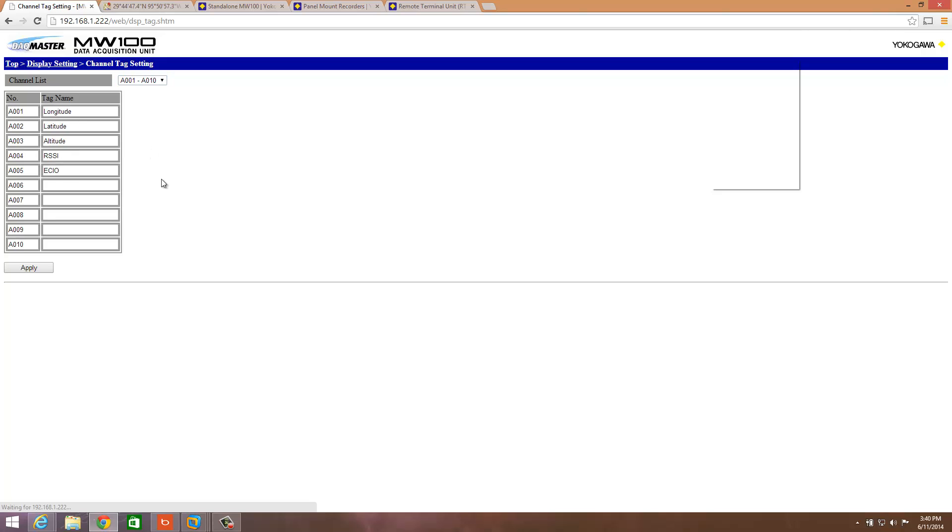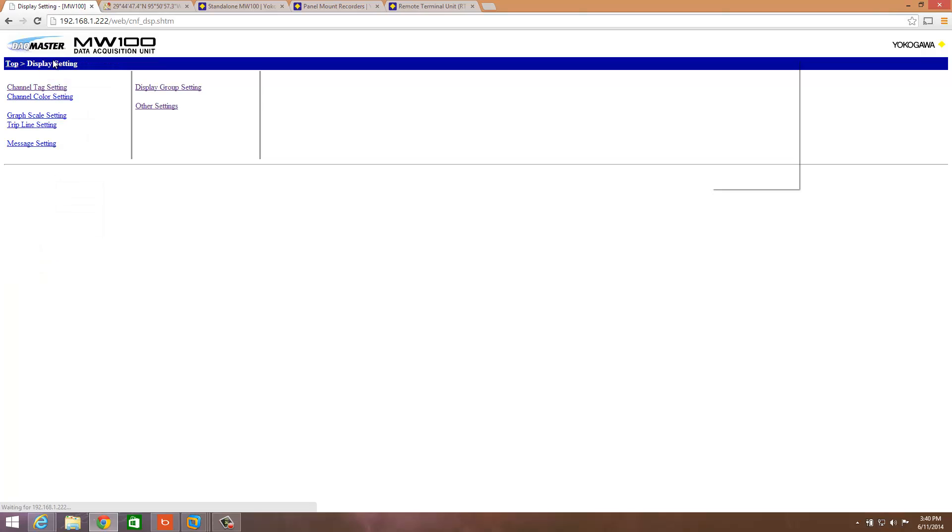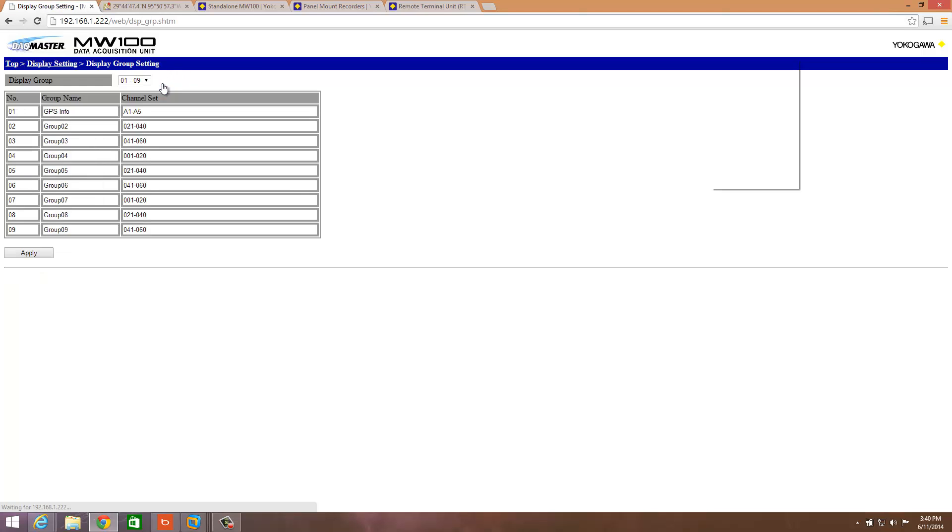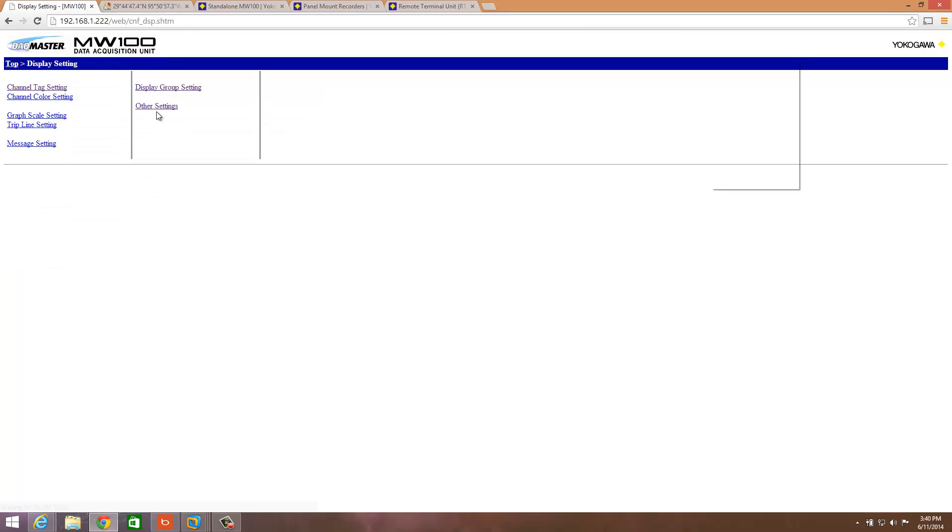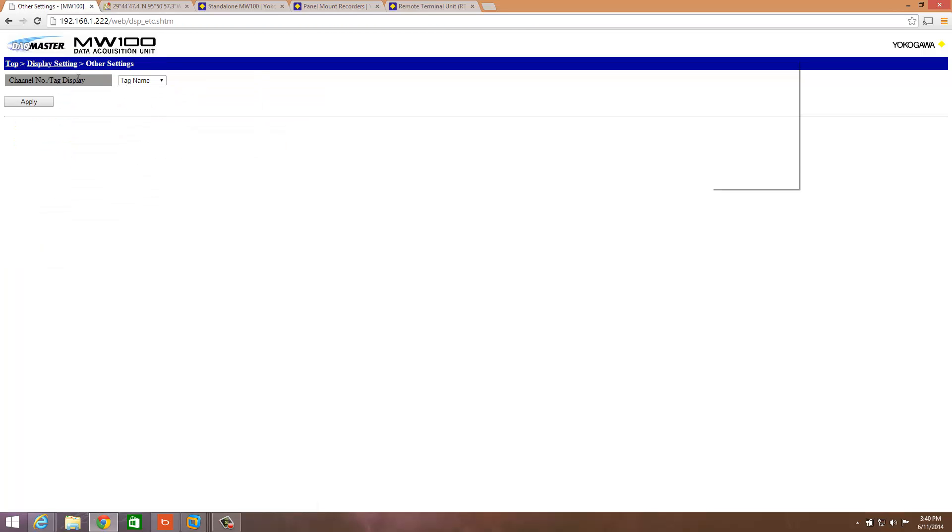The next place we're going to go is over to Display Settings, to Channel Tag Settings. We're going to go down to the math channels and put in the tag names and apply. We're going to go over to Display Group Settings. We're going to create a group. I called it GPS Info, and I said channels A1 through A5 to correspond to the math channels I set up. Under other settings, we're going to make sure it's display by tag name and hit Apply.